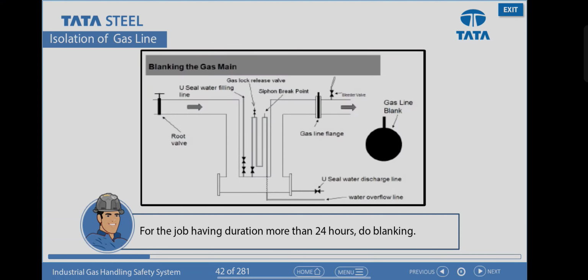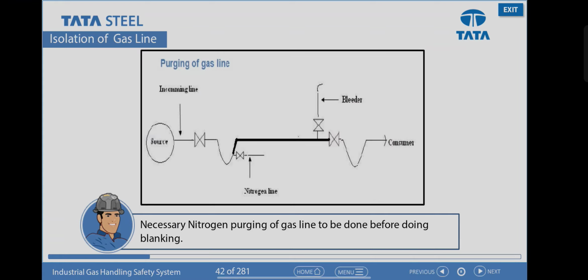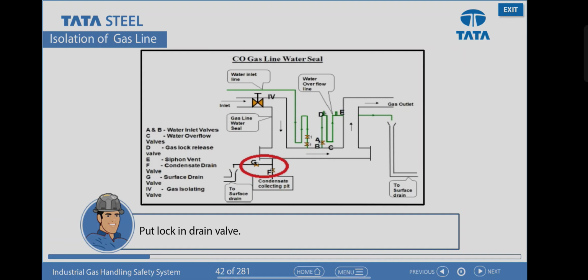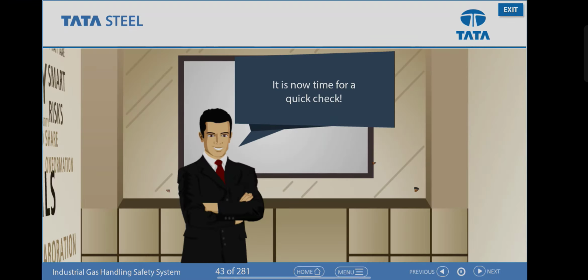For the job having duration more than 24 hours, do blanking. Necessary nitrogen purging of gas line to be done before doing blanking. Put lock in drain valve. It is now time for a quick check.